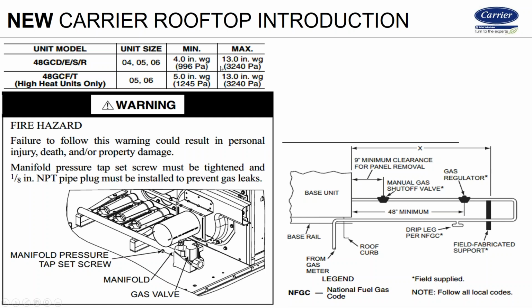Up here, here's your inlet pressures. That's in the book, so it gives you all the information there. If you got high pressure coming in from the meter and you need a regulator to take it down to your 5 to 10 inches manifold inlet, make sure the gas regulator is 48 inches or at least far enough away from the exhaust as possible.